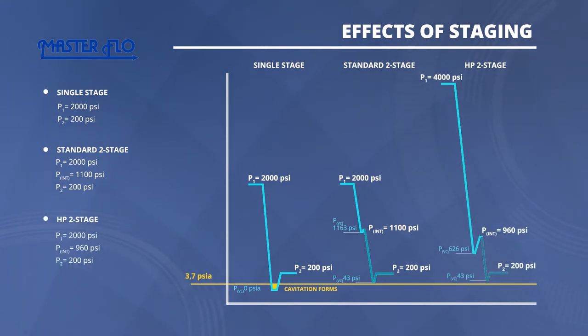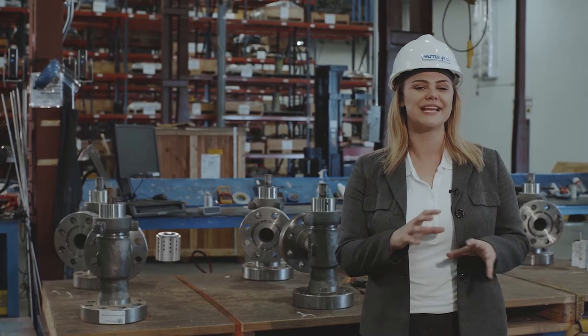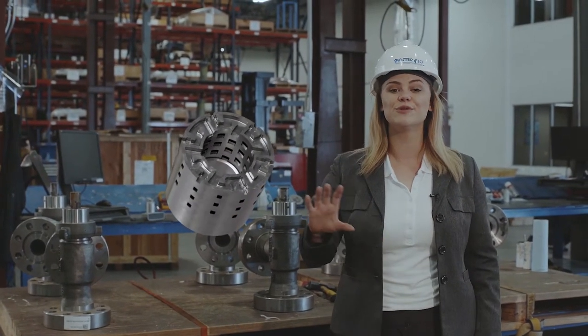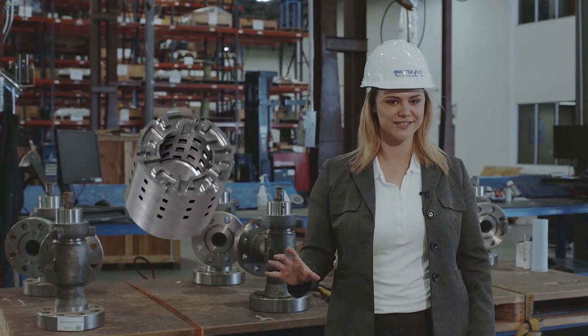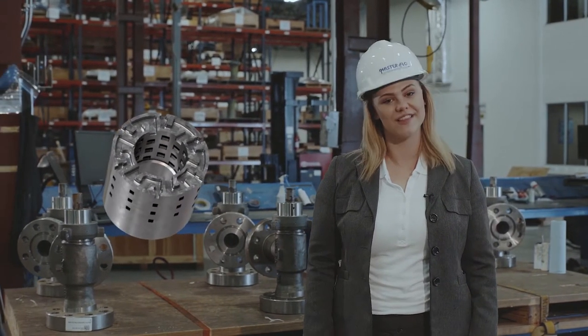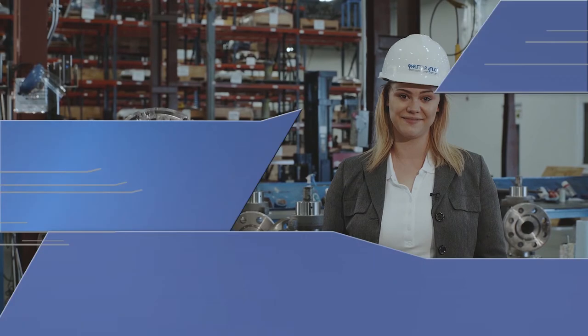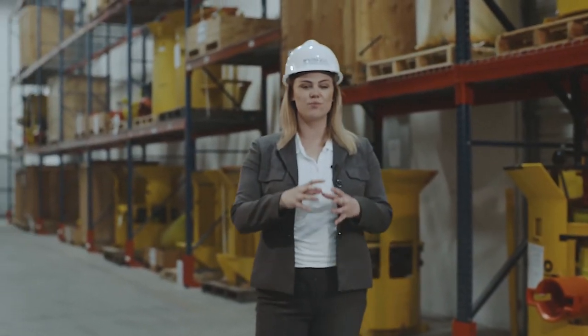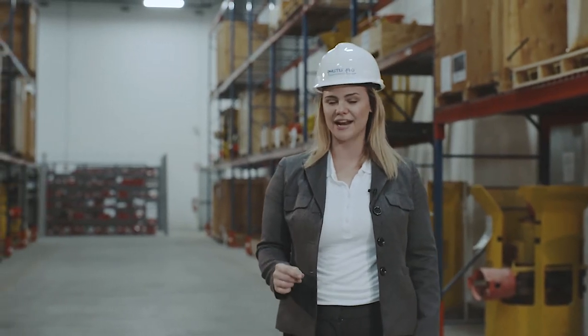When more than two stages are needed, a labyrinth-style trim is employed. It features an internal plug and a labyrinth cage that allows a smooth transition between cage ports, and controls the velocity throughout the labyrinth. These trims are available for liquid, gas, and multi-phase applications. The trim cage is compression-loaded and constructed as a solid element of tungsten carbide for durability and ease of service.